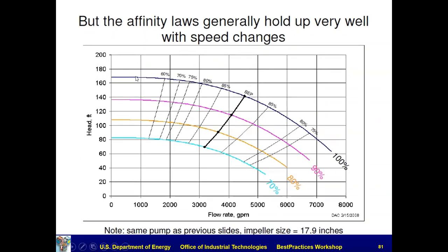So this would be a pump curve that you would get for 100% speed from the manufacturer. And that speed would probably be something like 1550, 1560 RPM, whatever they chose to publish it at, okay? And then at 90%, it would be 90% of 1550. This would be 80%, 70% as you slow that thing down. So you see what happens when you generate these curves in Excel. You take this curve and you pick points off of the actual published pump curve.